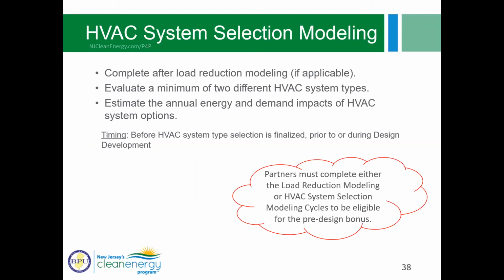All right, so the next modeling cycle. Like I said before, for the P4P program, either what we just discussed, the load reduction modeling cycle with the simple box and the conceptual model, are required, or the HVAC system selection modeling. And I find this very fun to model. You want to complete this after the load reduction, if it's applicable, and you want to evaluate at minimum at least 2 different HVAC system types. You want to estimate the annual energy and demand impacts of the different options. You want to do this prior to or during design development, but before the HVAC system type has been selected.